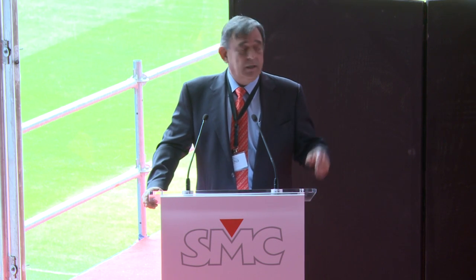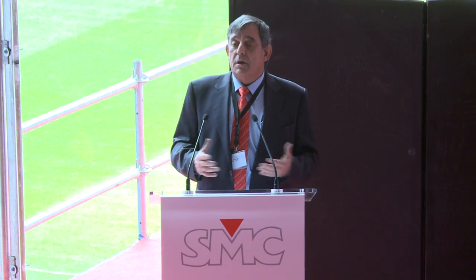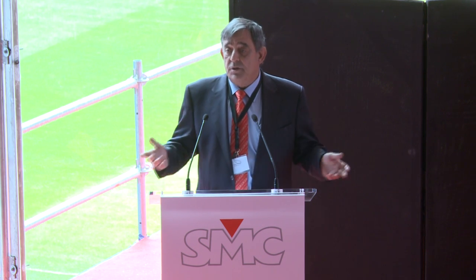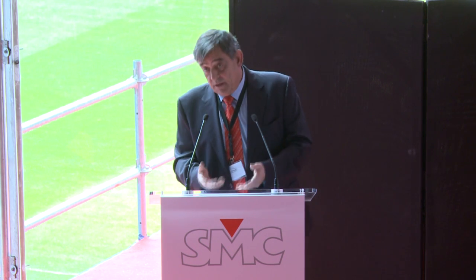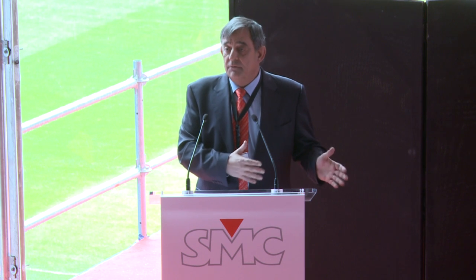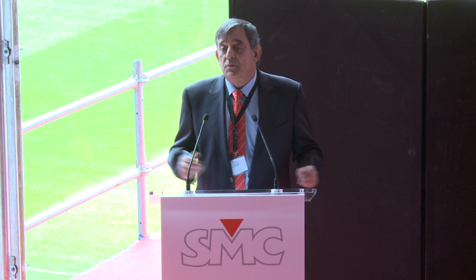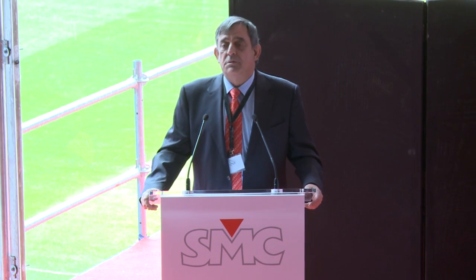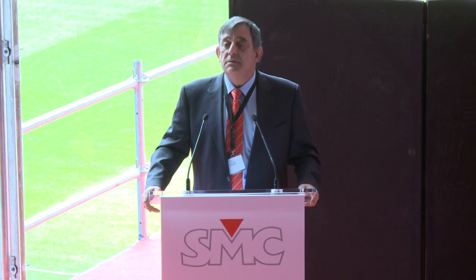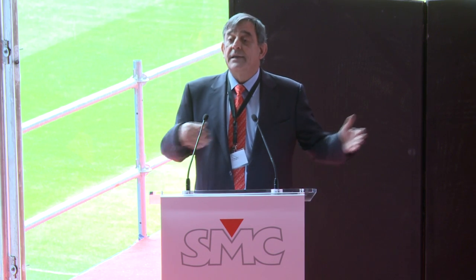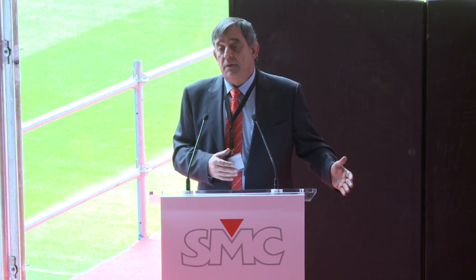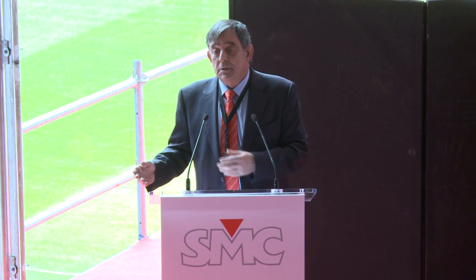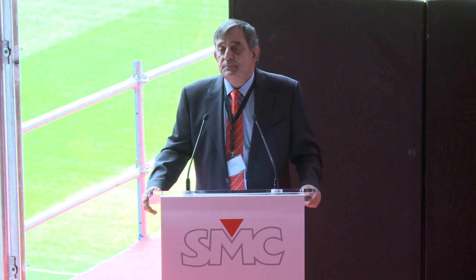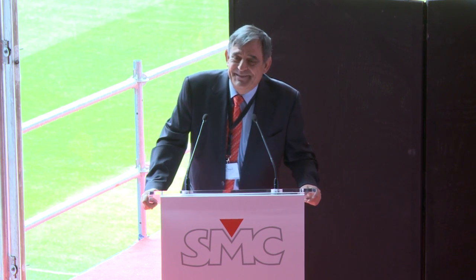Also, the master unit has the ability, when working alone without injecting high current, or even when injecting high current by itself, to use a variable frequency selectable between 20 and 400 hertz. So we are able to make sweep frequency runs for defined tests. Of course, when you connect a slave, the slave is supplied from the main supply, so it's only main supply. Thank you.